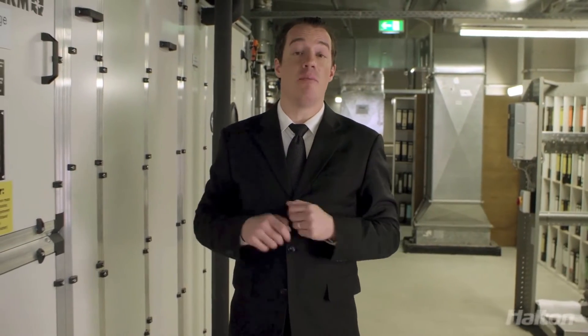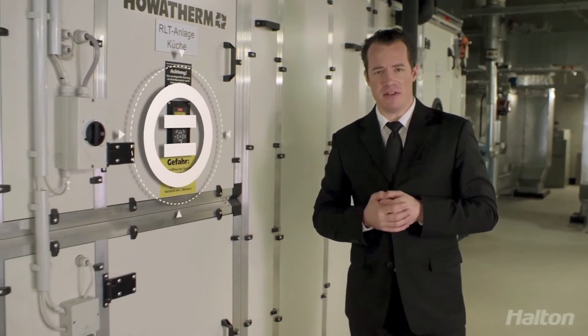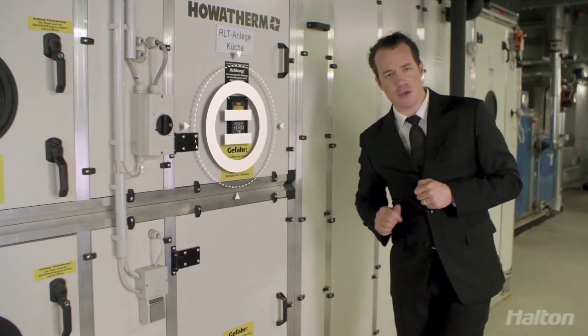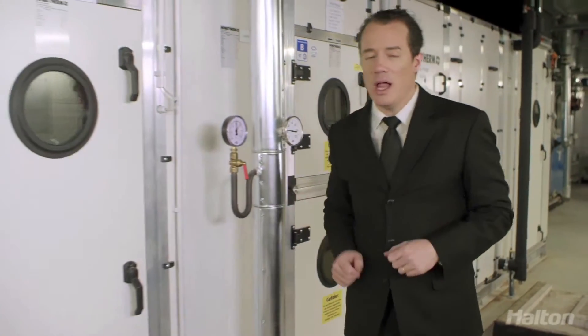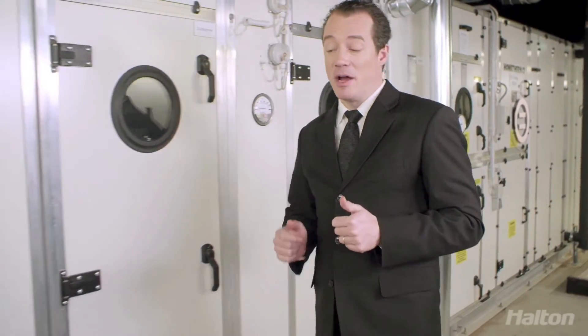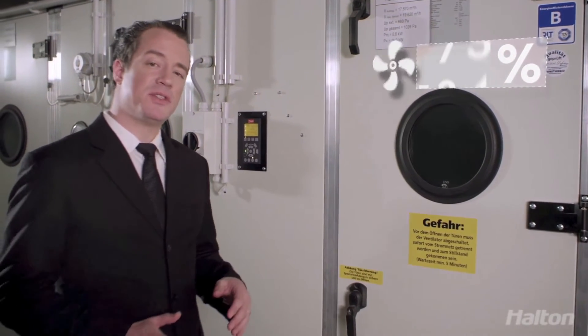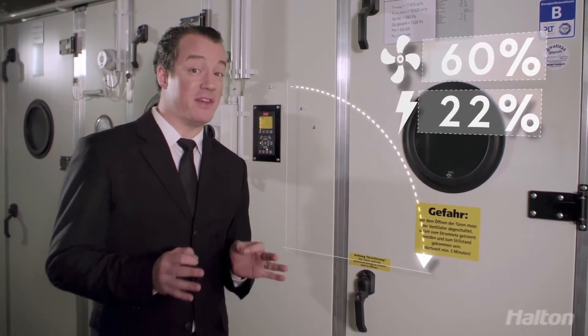Just three floors above the kitchen, exhaust fans consume a significant amount of energy. The speed of the fans is traditionally controlled to keep the pressure in the ductwork at the same level. But Marvel also adjusts the pressure by reducing the speed of the fans to an absolute minimum level. And that really is the cherry on the cake — if the fan speed decreases to, say, 60%, its energy consumption falls to only 22%. Fan speed adjustment can be the source of massive savings.